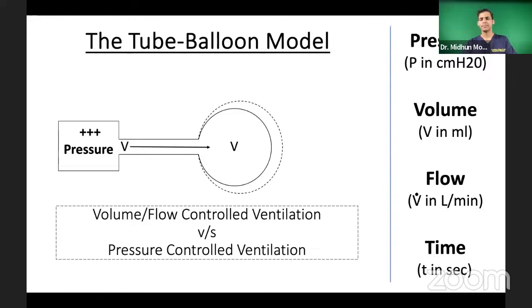See, what am I controlling here? I am controlling the volume here, all right? But I'm not controlling the pressure. The pressure is being generated by the machine to deliver this much volume. So if I'm controlling the volume, it's called volume controlled ventilation or volume targeted ventilation. But I'm not able to control the pressure here. Suppose I'm giving 500 ml of tidal volume and the pressure goes to around 40 centimeter water. This is going to be dangerous, because anything more than 30 centimeter water pressure can result in barotrauma. So I want the ventilator to reduce the pressure. I want to control the pressure here to prevent barotrauma. So I'm setting on the ventilator that whatever happens, you give only 20 centimeter water pressure or even 30 centimeter water pressure. Now the ventilator generates only that much pressure.